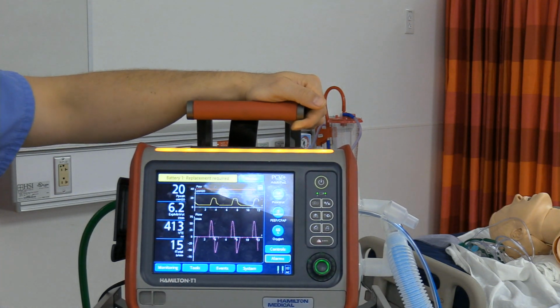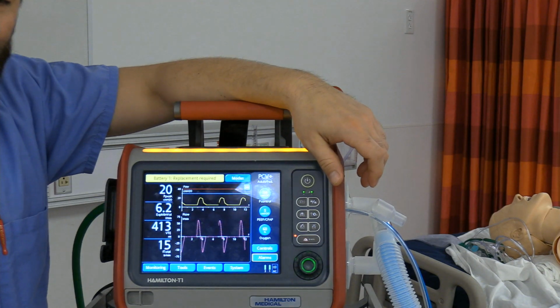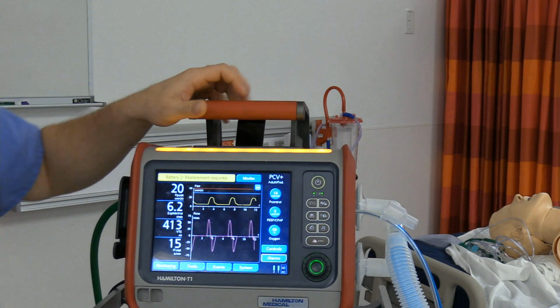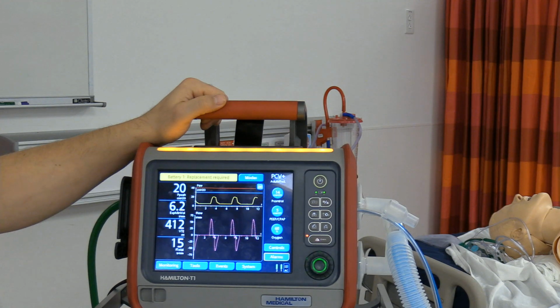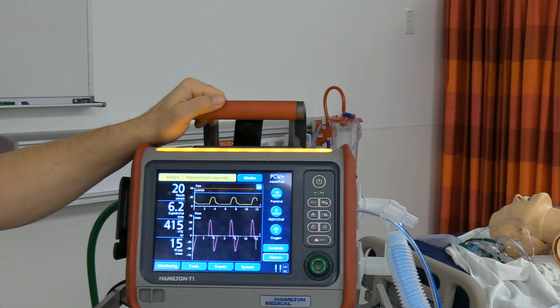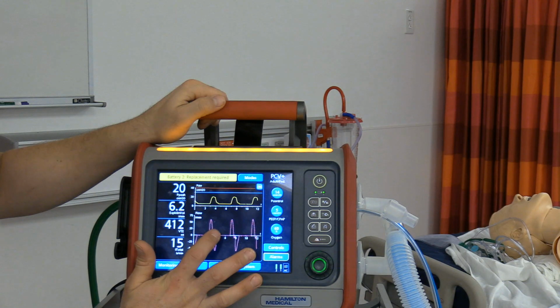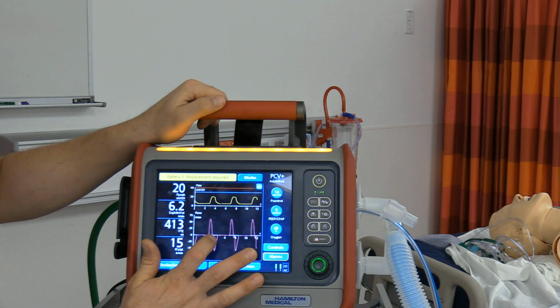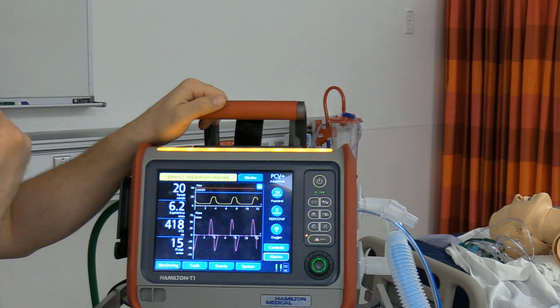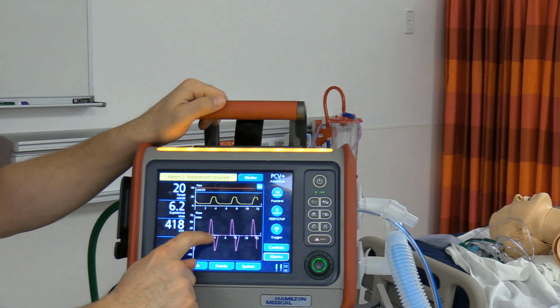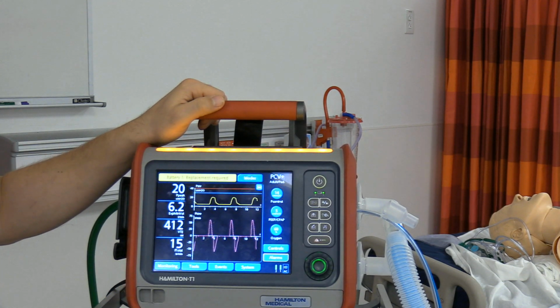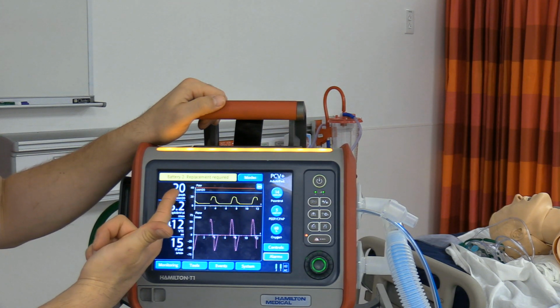One thing I want to point out, and it's not as important on pressure ventilation, is volume, although some people would argue that. But we can't check a plateau pressure on this ventilator. I would assume the rationale is it's all pressure ventilation. So as long as you're proficient at reading these flow waveforms and recognizing what we'll learn later on, that you got total flow equilibration between, or total pressure equilibration between your Y, or the patient connection, and the patient. Because at the end of that breath, we were at a 0 flow point. I could assume that my peak and plateau are pretty close.